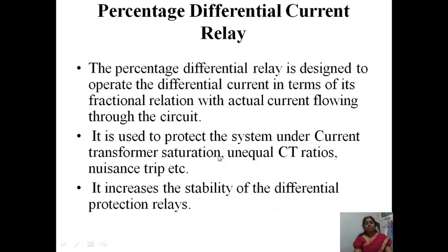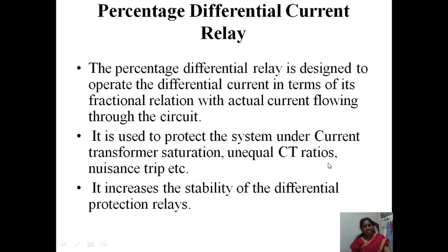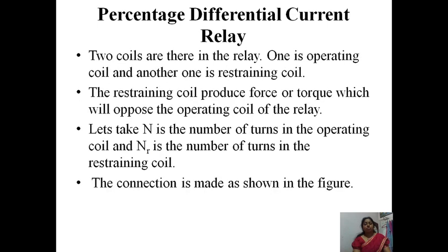This is the biased or percentage differential relay. The percentage differential relay is designed to operate based on the differential current in terms of its fractional relation with the actual current flowing through the circuit. It is used to protect the system under current transformer saturation, unequal CT ratios, nuisance trip, etc. It increases the stability of differential protection relays.